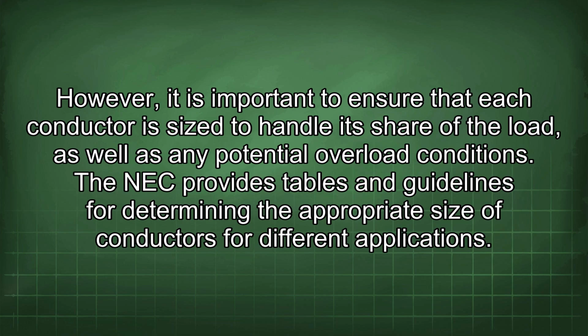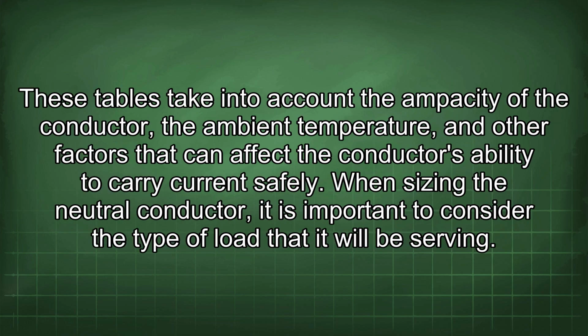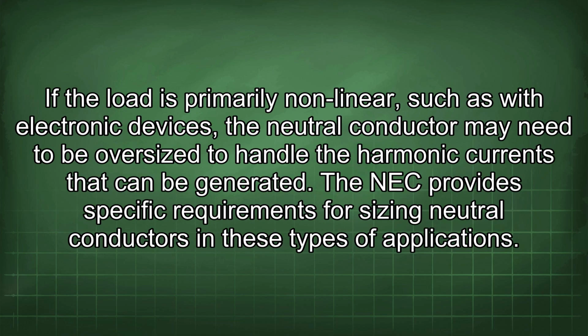The NEC provides tables and guidelines for determining the appropriate size of conductors for different applications. These tables take into account the ampacity of the conductor, the ambient temperature, and other factors that can affect the conductor's ability to carry current safely. When sizing the neutral conductor, it is important to consider the type of load that it will be serving. If the load is primarily nonlinear, such as with electronic devices, the neutral conductor may need to be oversized to handle the harmonic currents that can be generated. The NEC provides specific requirements for sizing neutral conductors in these types of applications.